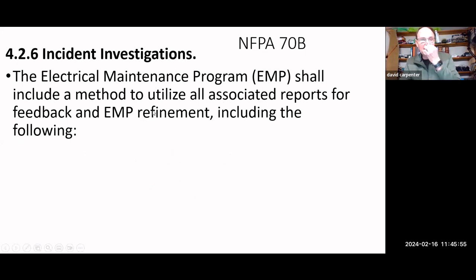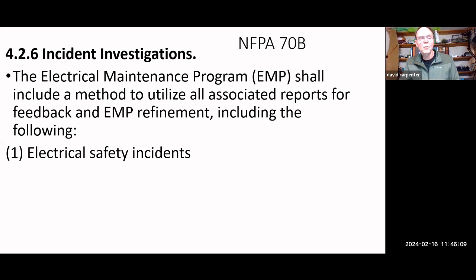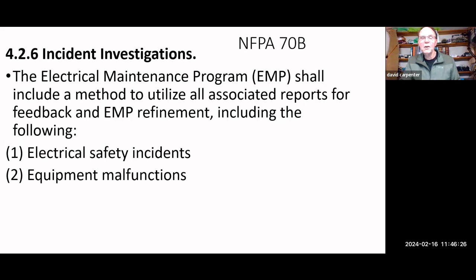So an incident investigation is found in 4.2.6 in NFPA 70B, which is the new maintenance standard that's kind of hitting pretty quick right now. And it's basically the same as what we saw before. But you want to look at a couple of things. First of all, you want to look at any safety incidents that they've had, and you've got to report it. Second, any malfunctions. So if they've had a malfunction with a piece of equipment that could have caused or even started an arc, or maybe it did something, they need to report that. That includes anything related to shock, fire, or arcs.